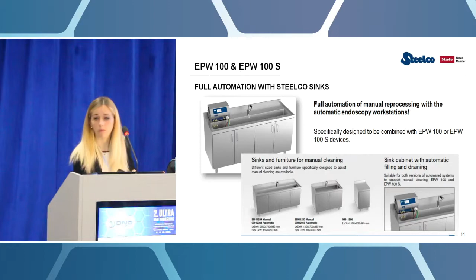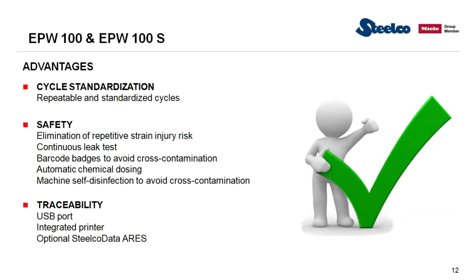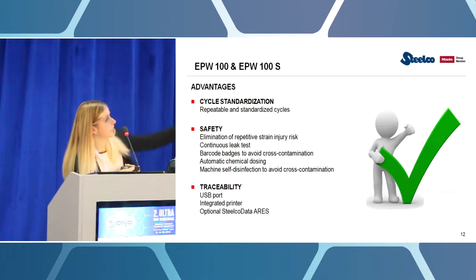And of course, this also provides safety for all of you. Safety because we have the elimination of repetitive movements and strain injury risks. Leak test is completely automatic. So if there are some leakages in the scope, the machine will stop and it will enable you to take out the scope and send it to maintenance without compromising the instrument itself. And then traceability. Here you can see you also have a set of badges to operate this kind of machine.